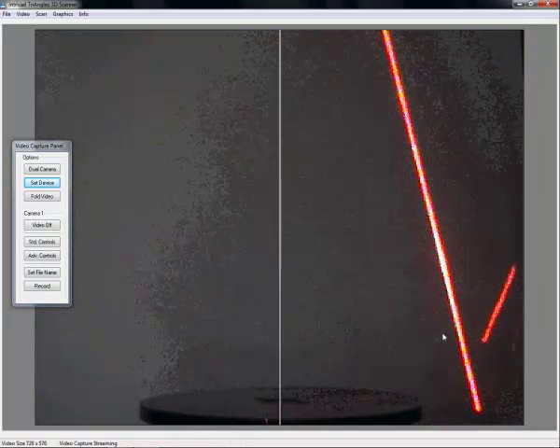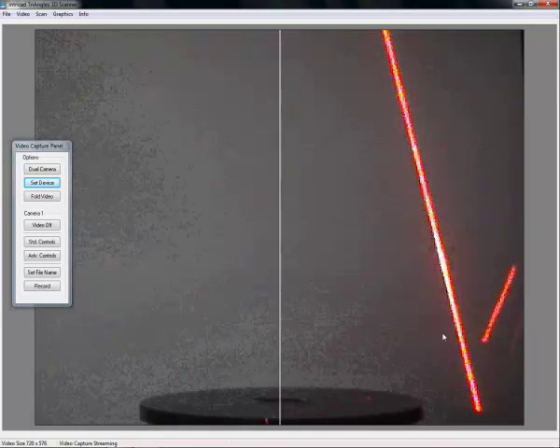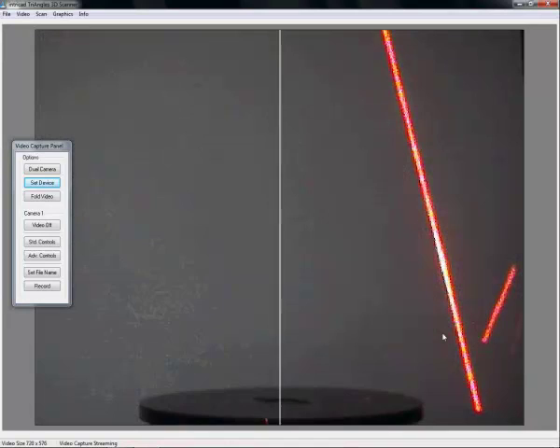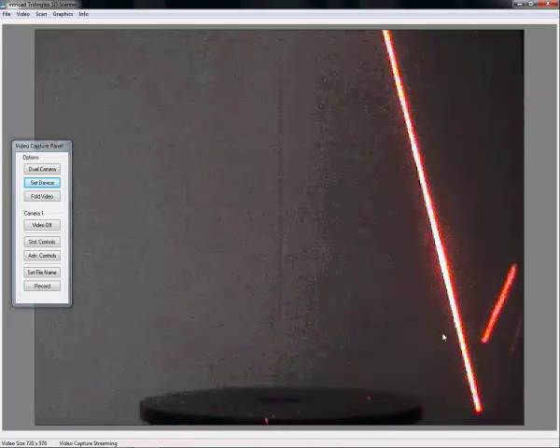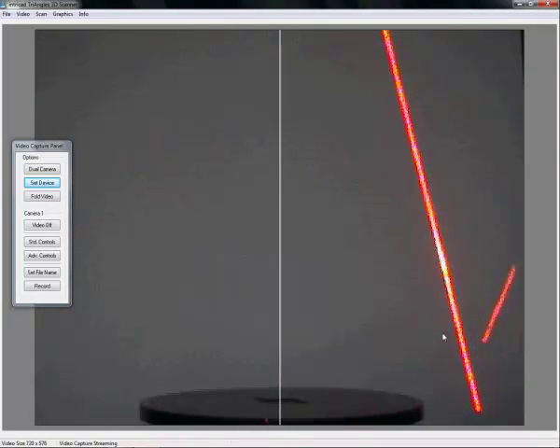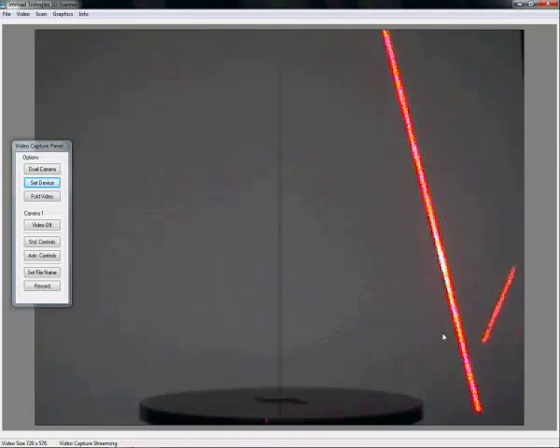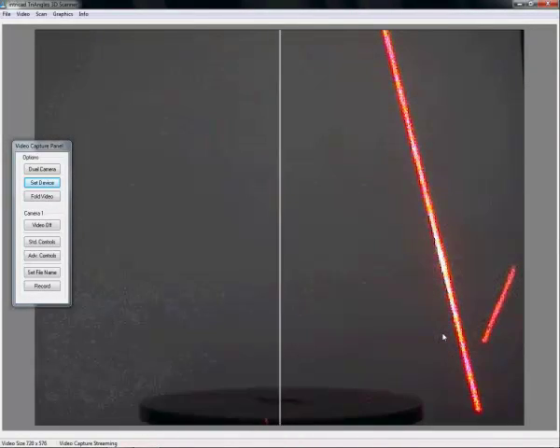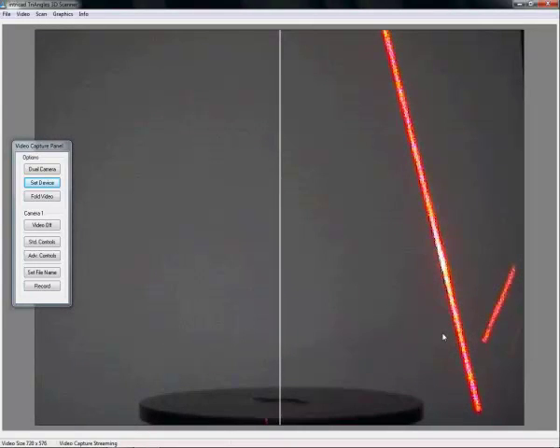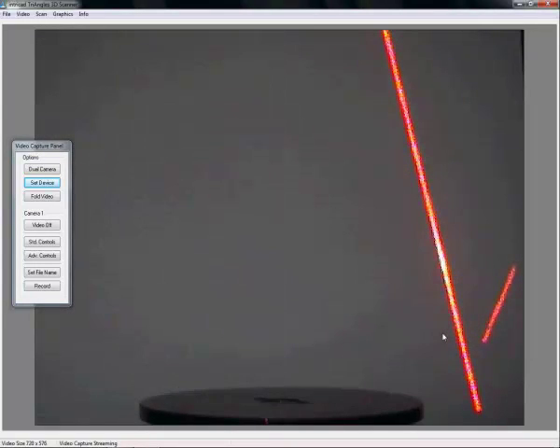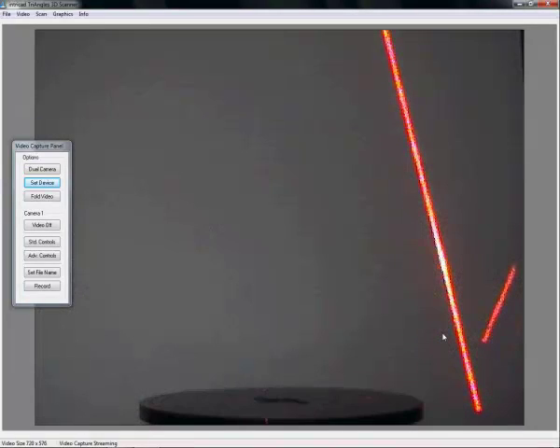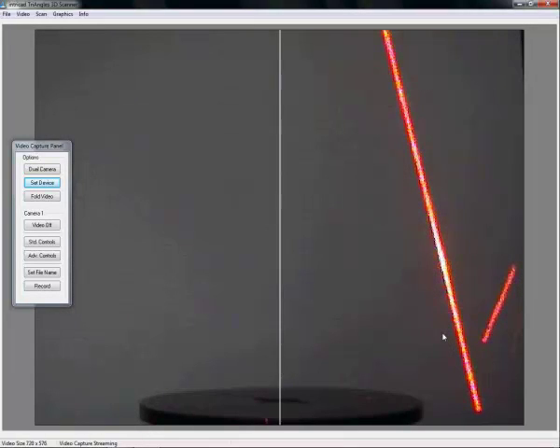Again, don't worry about the angle of the laser. The next thing we have to do is to make sure that the laser line is perpendicular to the disk. To do this we use the calibrator that you have in your kit. These can come in various shapes and sizes. They all have the same function, they all work the same.